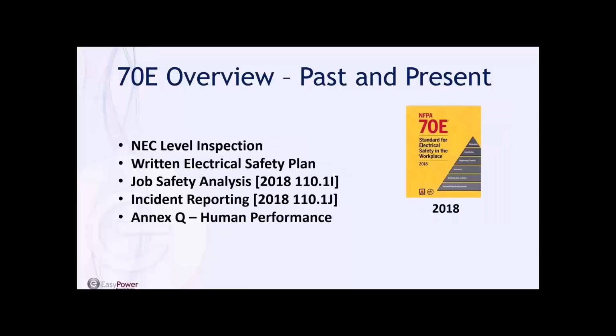Which brings us to the 2018 standard. As we touched on, the electrical safety plan was one of the key new initiatives. Inside the electrical safety plan was a new reference to NEC level inspections — new equipment and modifications to the electrical system should be inspected, with an inspection report confirming devices have been installed to the standards of the National Electric Code. Also new in 2018 was job safety analysis and incident reporting, two additional elements that go into the electrical safety plan.